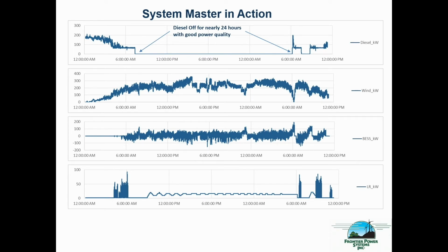And underneath the BESS, we can see how the load regulator operated. It did some corrections during the time the BESS was operating, but the BESS carried the majority of that. What it really did was, just before the diesels turned off and right after they came back on, the load regulator showed its worth.